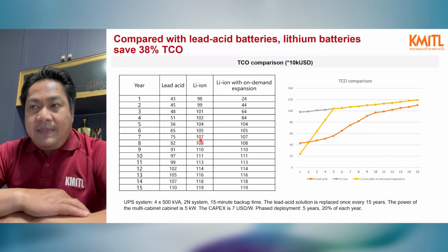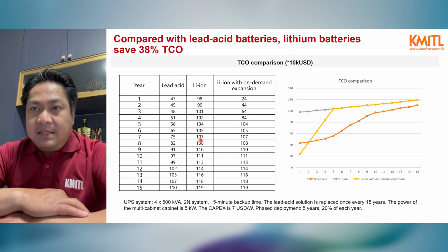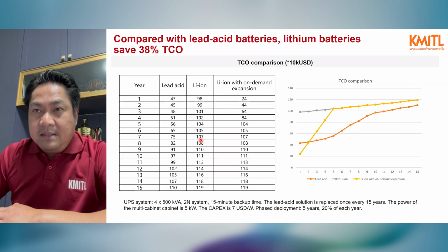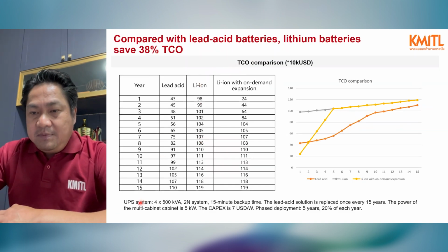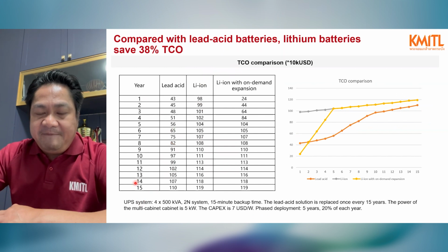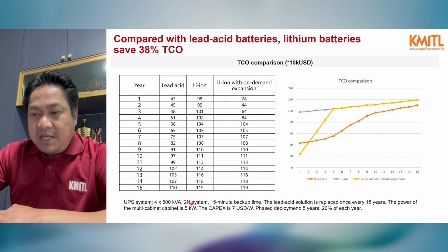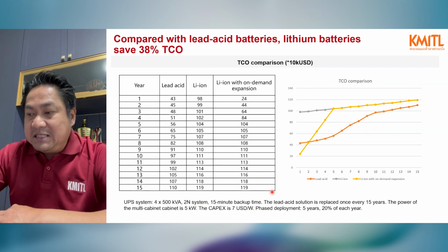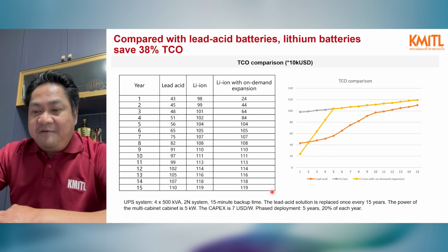When comparing lead acid battery and lithium battery, lithium will save about 38% of total cost of ownership. This test runs for 15 years comparing lead acid, lithium-ion, and lithium-ion with on-demand expansion. They use a UPS system for 500 kVA with a 2N redundancy system and 15-minute backup. The lead acid solution is replaced once every 15 years. The power of the multi-cabinet is about 5 kilowatts, the capex is about $7 per watt, and the phase deployment is 5 years at 20% per year.